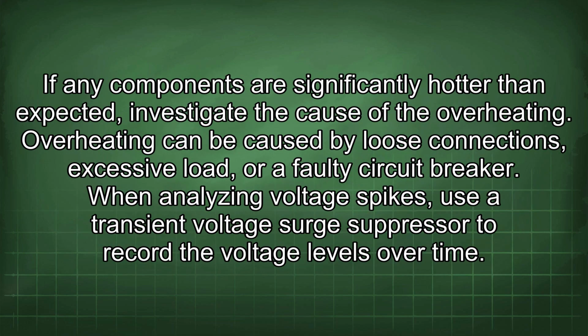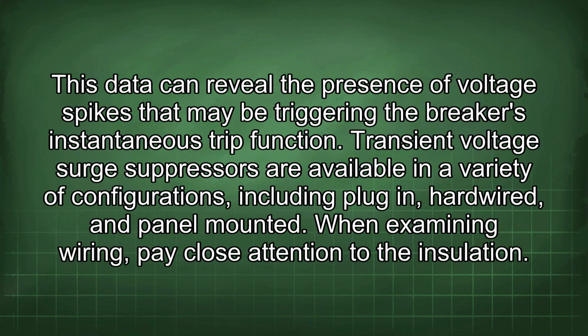If any components are significantly hotter than expected, investigate the cause of the overheating. Overheating can be caused by loose connections, excessive load, or a faulty circuit breaker. When analyzing voltage spikes, use a transient voltage surge suppressor to record the voltage levels over time. This data can reveal the presence of voltage spikes that may be triggering the breaker's instantaneous trip function. Transient voltage surge suppressors are available in a variety of configurations, including plug-in, hardwired, and panel-mounted.